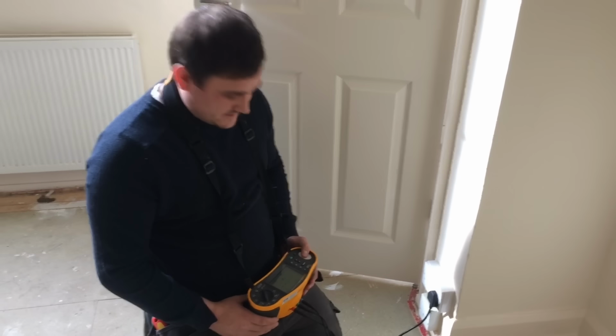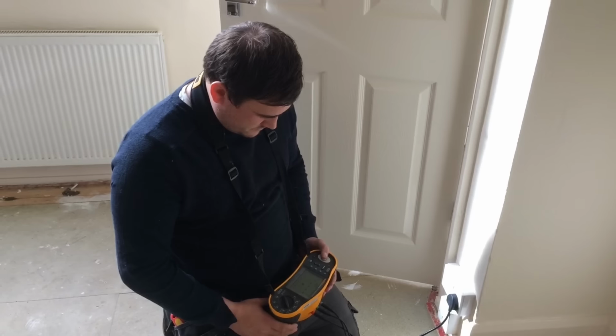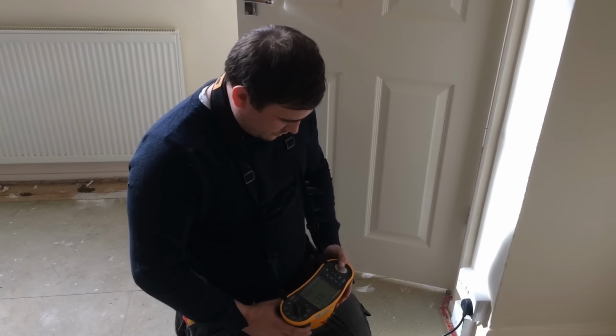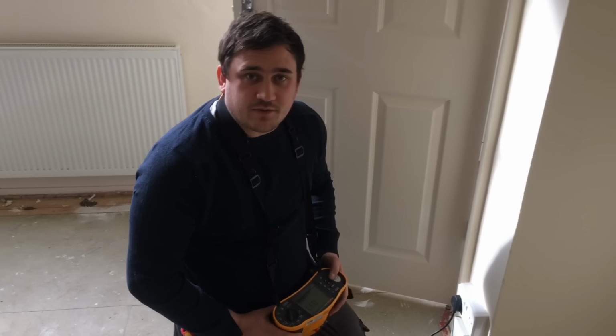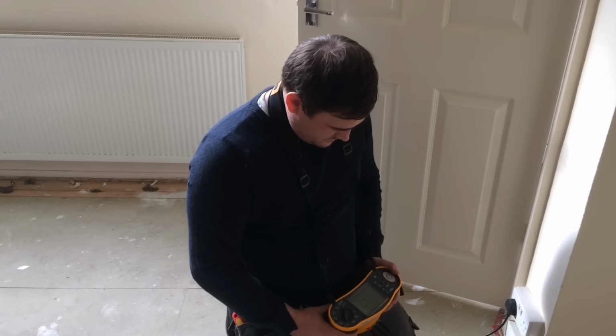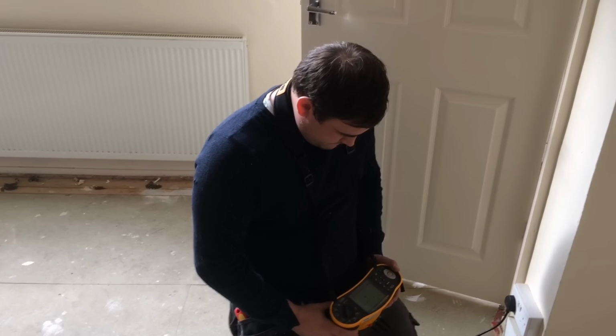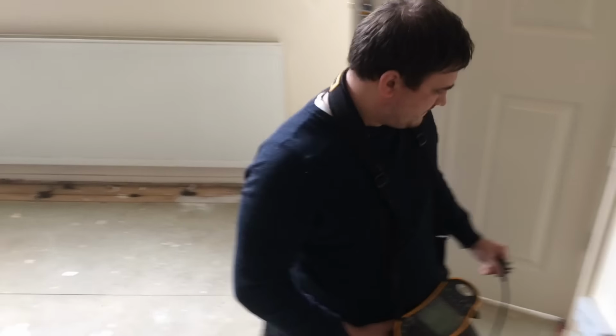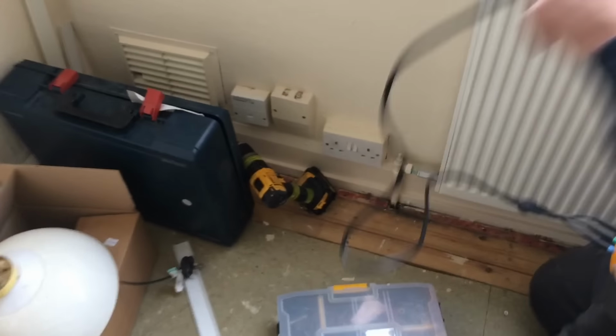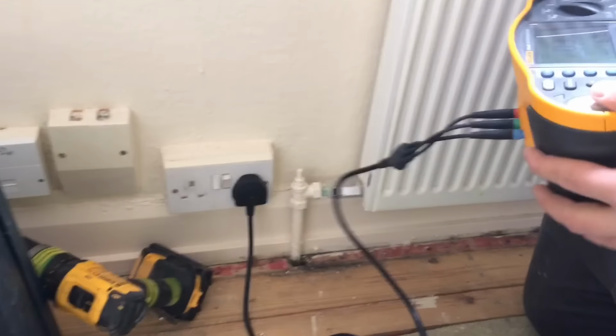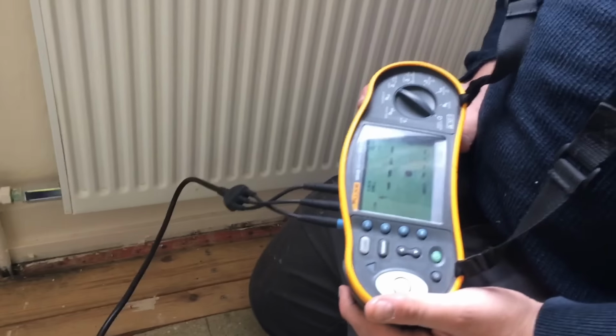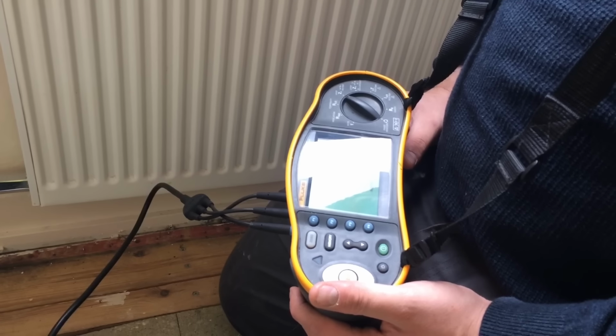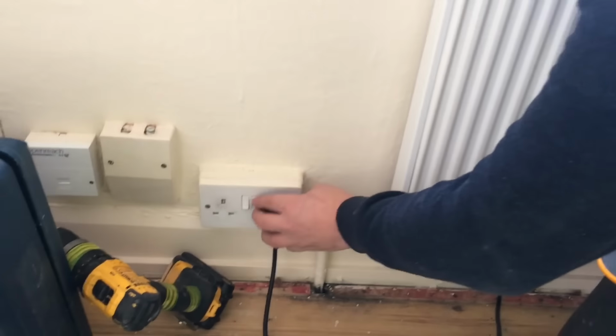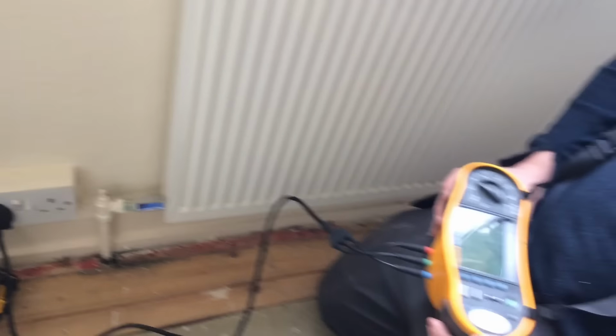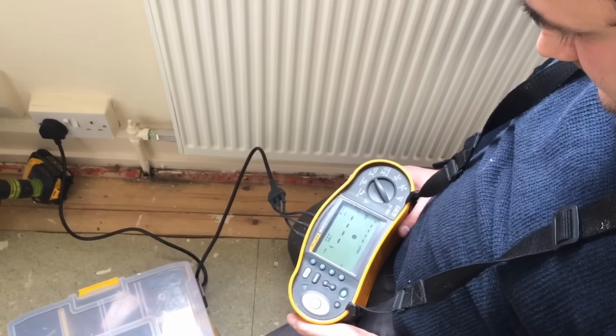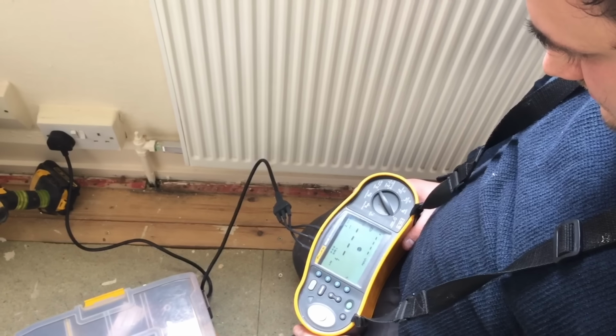Carrying on, we're now doing our ZS on our ring final circuit downstairs. We're using a plug-in lead tester this time. 0.37 ohms. We're going to do both sides of the socket as well. 0.36 ohms. We'll then check the values against our maximum ZS in our on-site guide. 0.42. Again, both sides. 0.41.